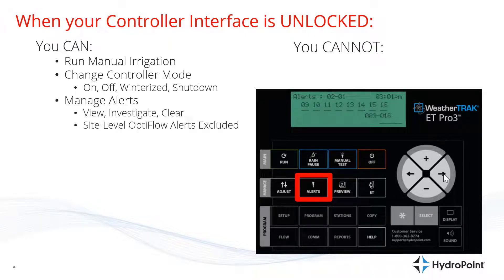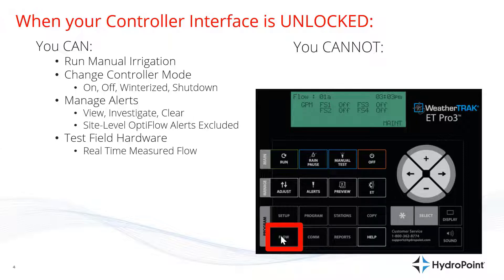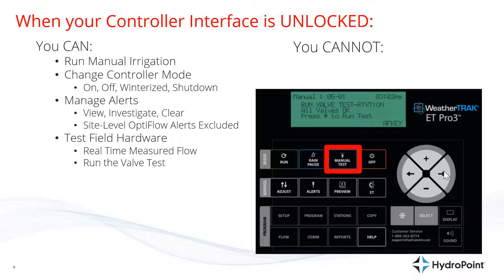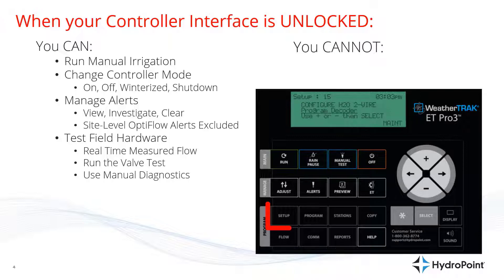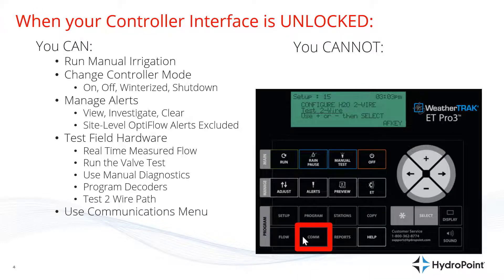Be aware that there are new site-level OptiFlow alerts that cannot be cleared from the panel. But unlocking a controller also enables all of the field testing hardware, like looking at the real-time measured flow when running stations to test the system — a very useful troubleshooting tool. You can also run the valve test and test all electrical components of your irrigation system, run manual diagnostics and see specific milliamps from station to station, and use the field hardware to do all your two-wire work like programming decoders and testing your two-wire path. Unlocking also gives you access to the full communications menu, which is useful for troubleshooting communication issues in the field.